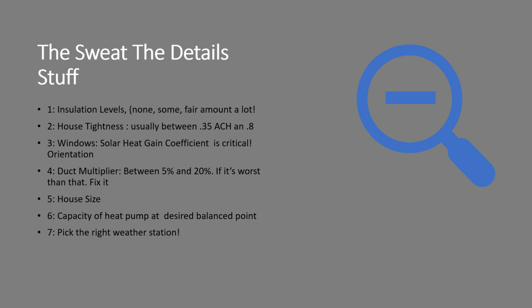House size is important, but not as important as insulation levels and window U values and window orientation. You need to know the capacity of the heat pump at your desired balance point. You can either do that by direct lookup or drawing the traditional balance point diagram. And also, don't forget to pick the right location. Remember where you live.